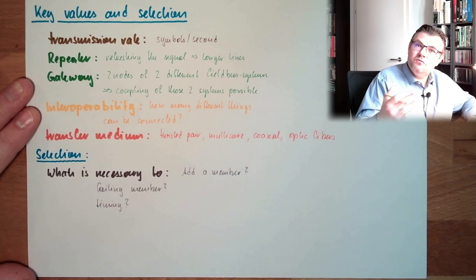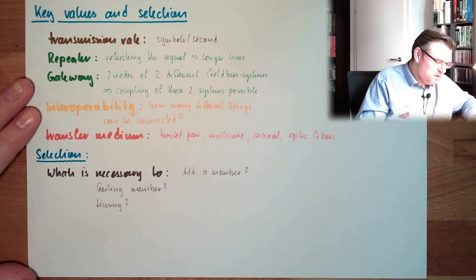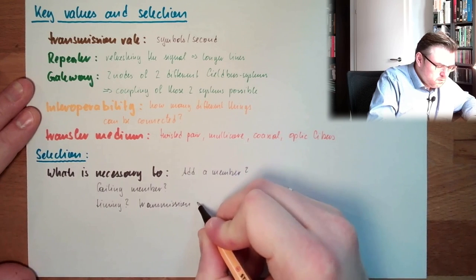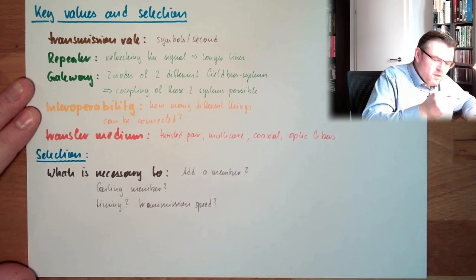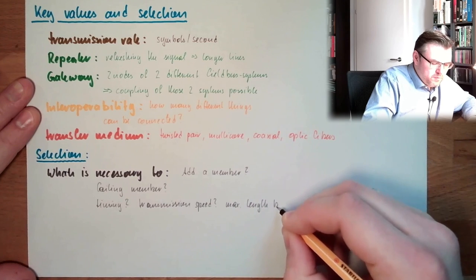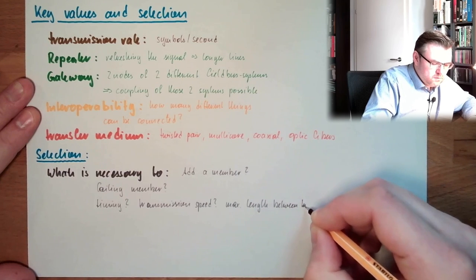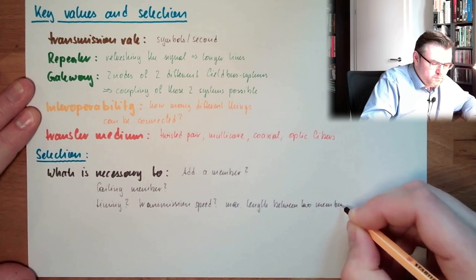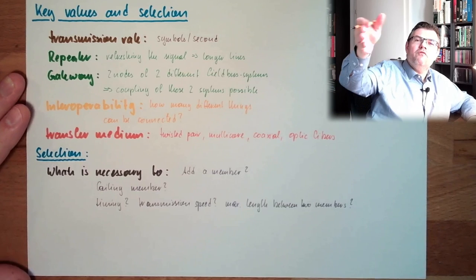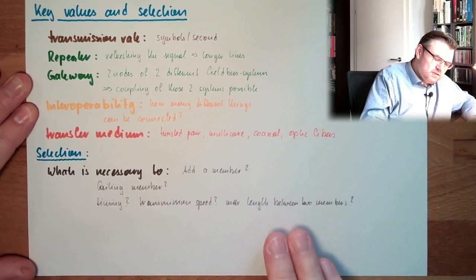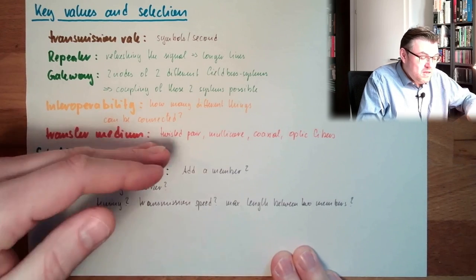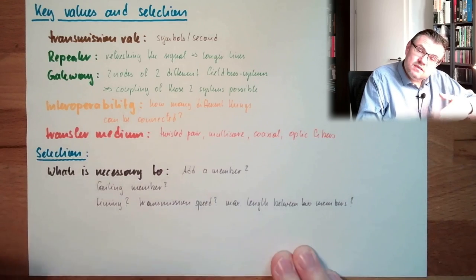What is the timing of our fieldbus system? What is the timing? Is it real time capable? Is it not real time capable? What is the transmission speed? What is the maximum length between two members? Usually we have some application in mind and then we know how far apart two members can be. Is this capable? Is this fieldbus system capable of managing this? Is a gateway necessary for instance? What transfer medium? Optic fibers usually have longer distances as possible.